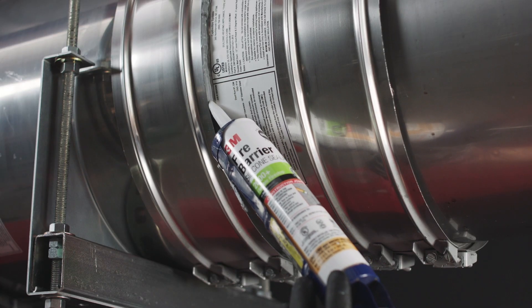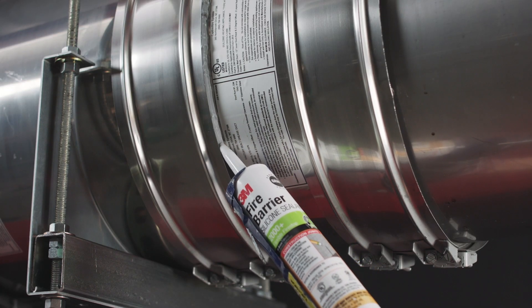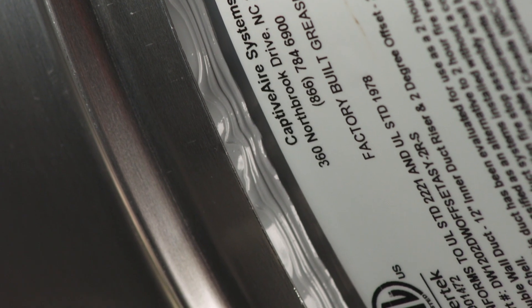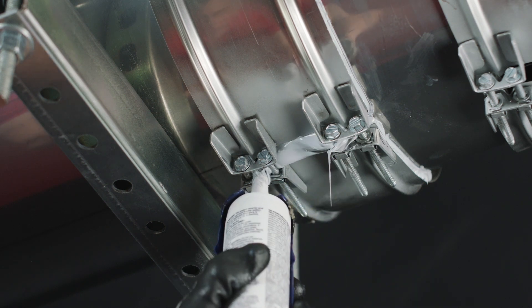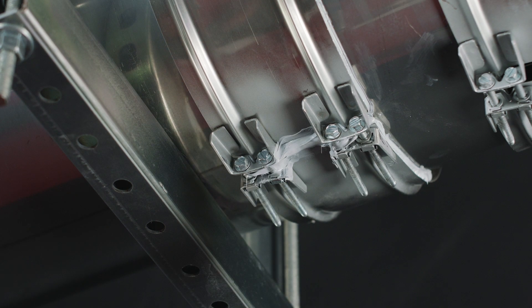For outdoor installations, you must seal all the outer double V-bands with a generous bead of sealant, all the way around the band. You must also seal the gap across the V-band hardware, and wipe off the excess sealant to achieve a finished look.